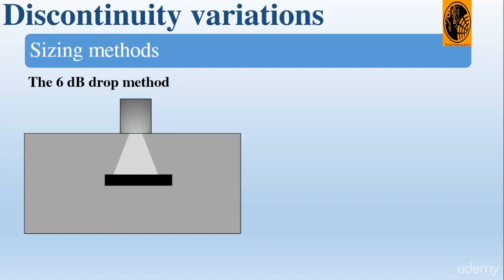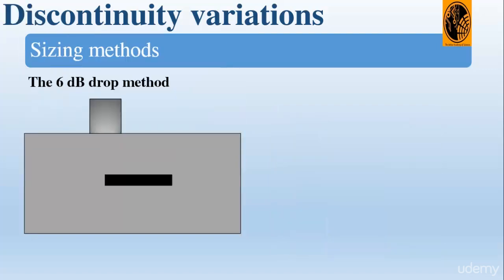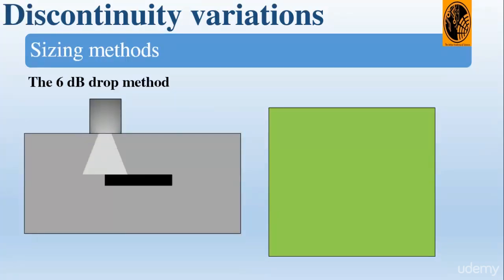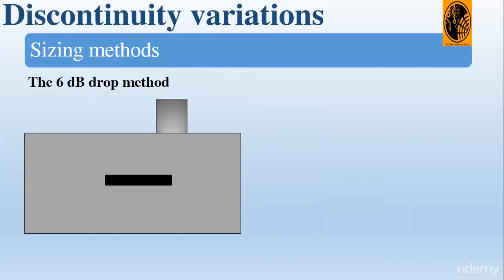As you can see on the screen, we have the sound beam directed to the reflector and we get the maximum signal at full screen height. If we move the probe until the amplitude of the signal drops by 50%, we can say that the edge of the reflector is on the center line of the beam. We do the same from the other side to determine the full extent of the reflector.